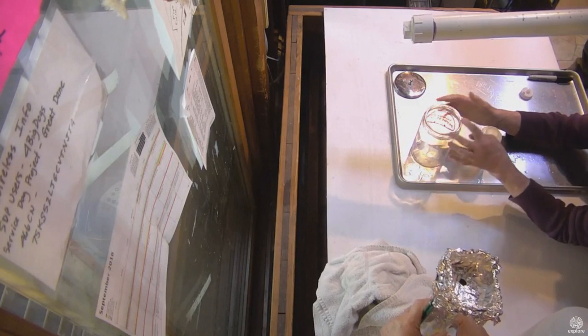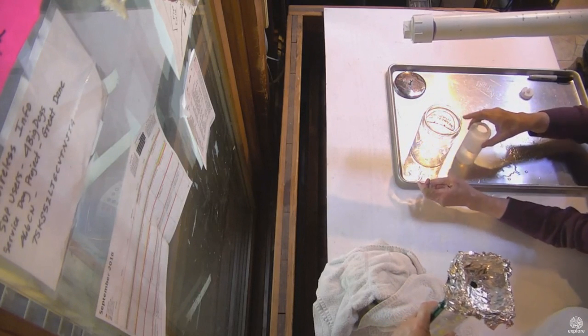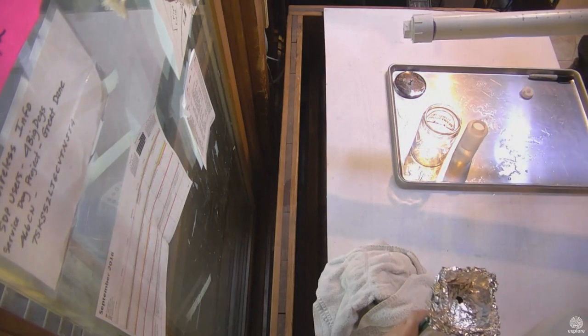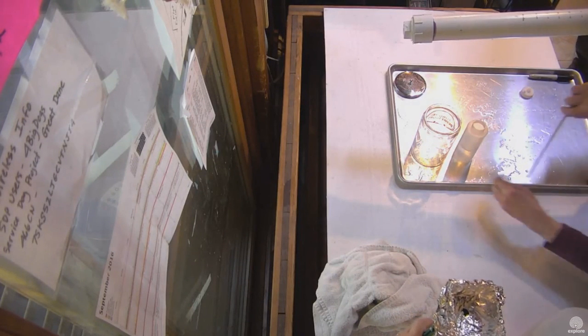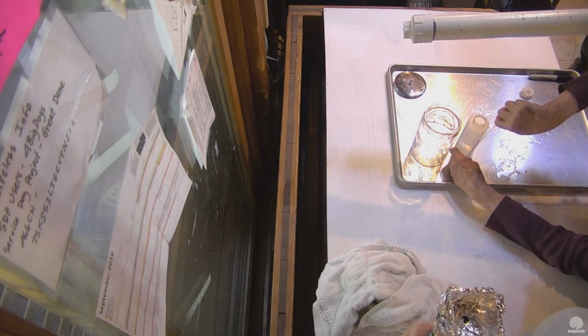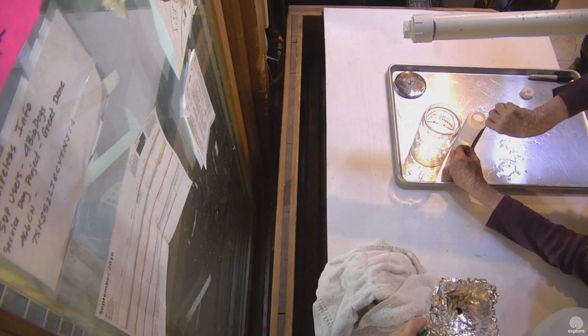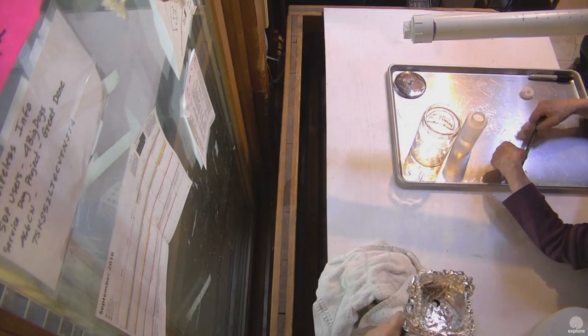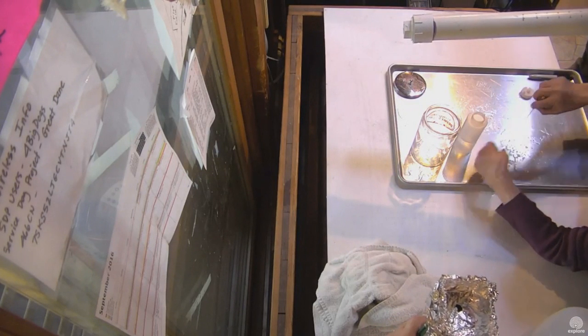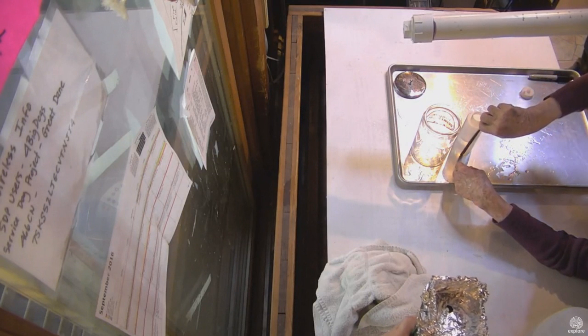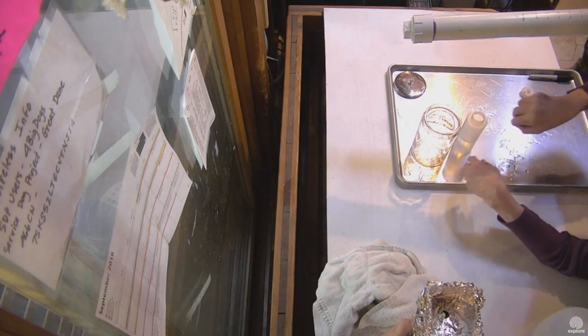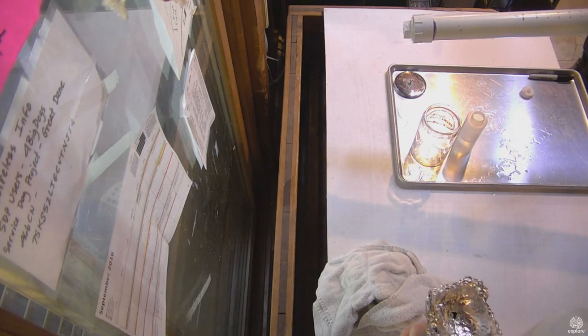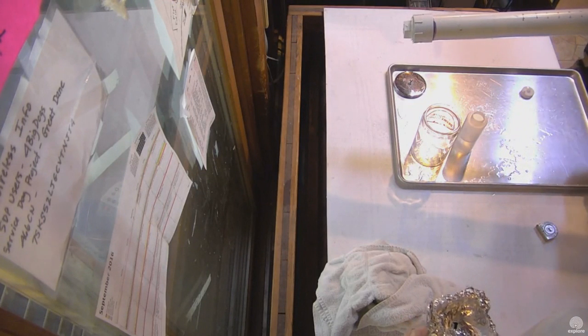Okay, so that 1 inch of water that fell in this area came up to whatever that is - oh lordy, that much. That's 2.5 inches in our calibration device. So if 1 inch...